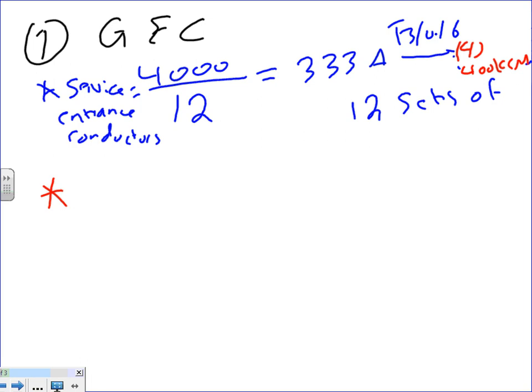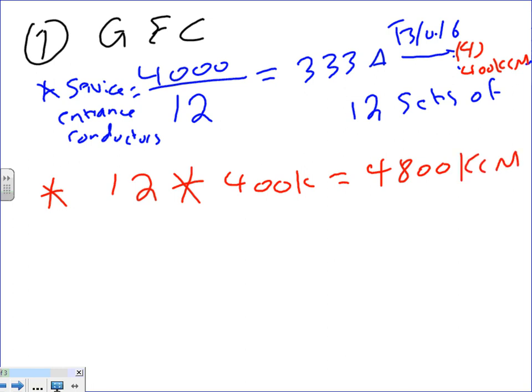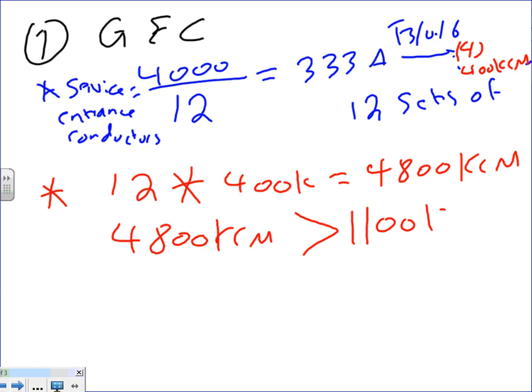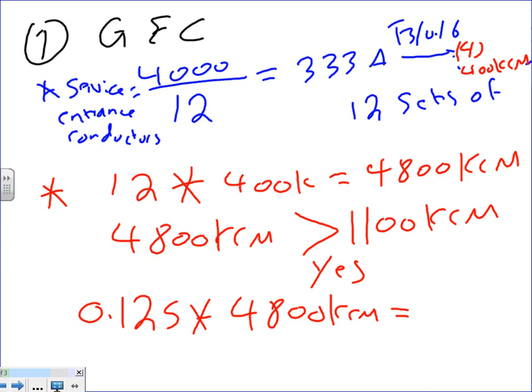Okay, the second thing, guys, if you look at the sheet that I gave you, how do you size the grounding electrode conductor? Are we paralleling? Yes, we're paralleling. So you take the 12 sets. Since we're paralleling, you're going to multiply the 12 sets by 400 kcm, and you're going to end up with 4800 kcm, if I did that right. And then you're going to ask yourself, is the 4800 kcm more than 1100 kcm? The answer is yes, right? Then you have to take 0.125 times 4800 kcm. If you do the math on that one, you're going to end up with, where are we here? Okay, so we take the 12.5%.